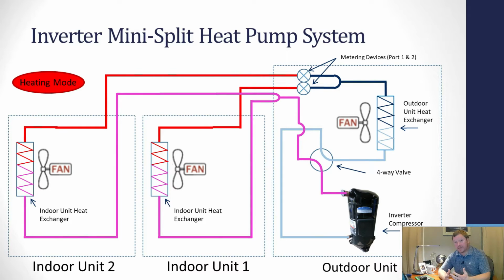And on most brands, again, this is going to change slightly from unit to unit, but on most brands, whatever the offset is, the same offset, doubled, is a safety to turn the unit off. And what I mean by that is when the unit gets to its target temperature of 73.5 in the living room, it doesn't shut off. The fan goes to low, but it keeps running. Again, this can change depending on model, depending on brand, but the general out-of-the-box functionality of mini-split systems is it gets to the target temperature and ramps the fan down to low, but it doesn't shut the fan off until it overshoots another 3.5 degrees. Whatever that offset was from the set point is generally the safety offset to shut the indoor unit off completely.